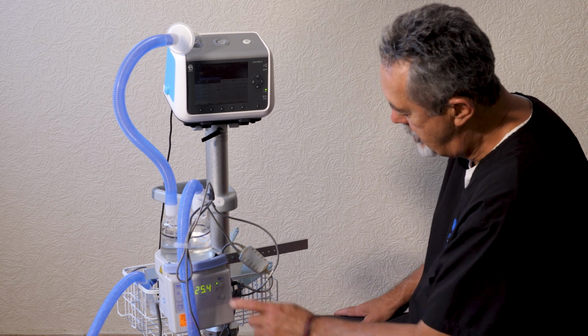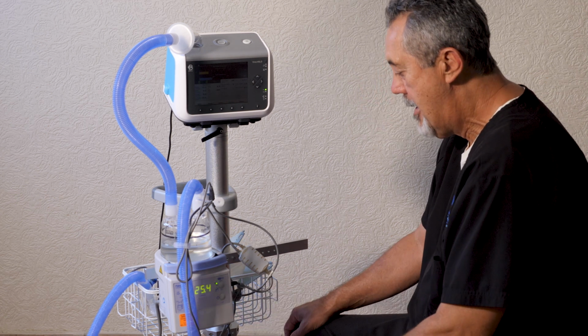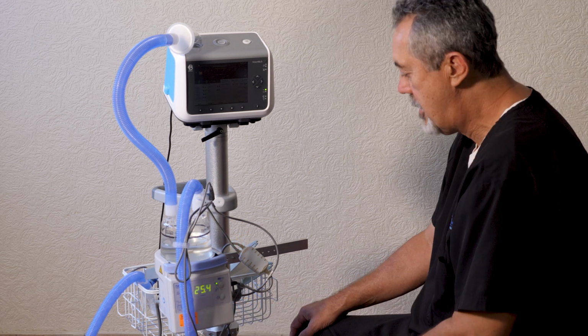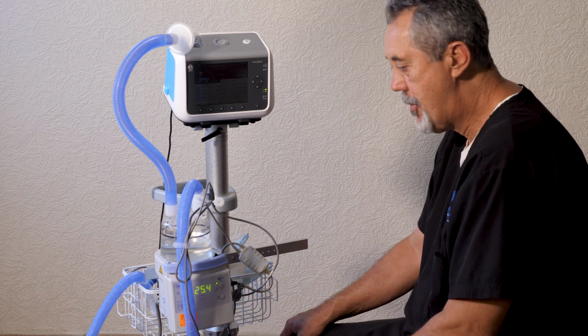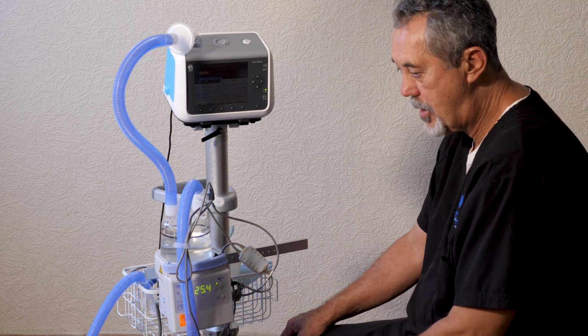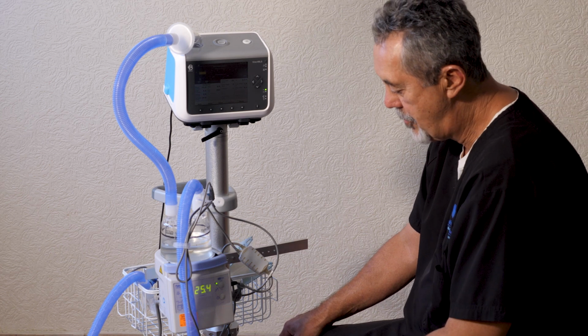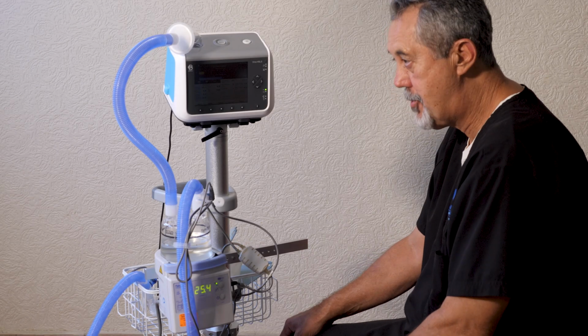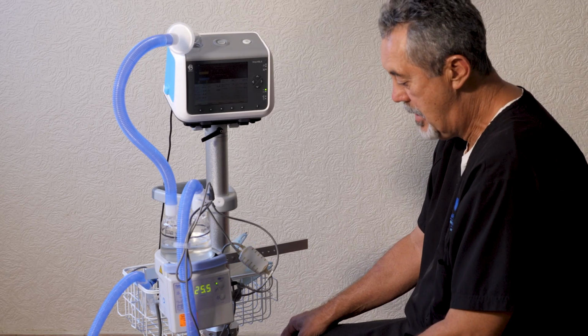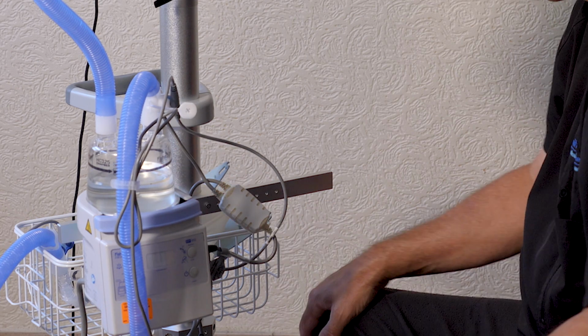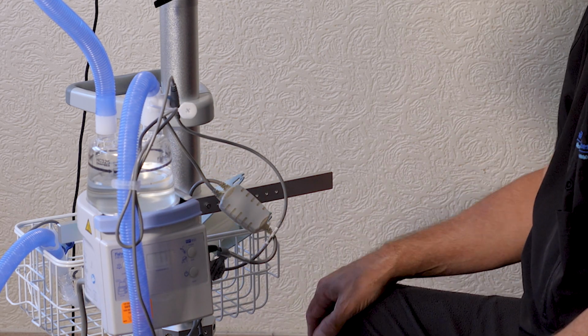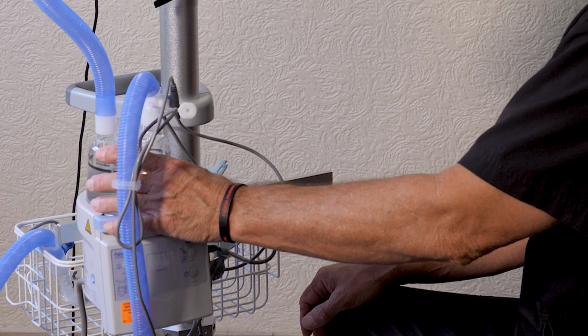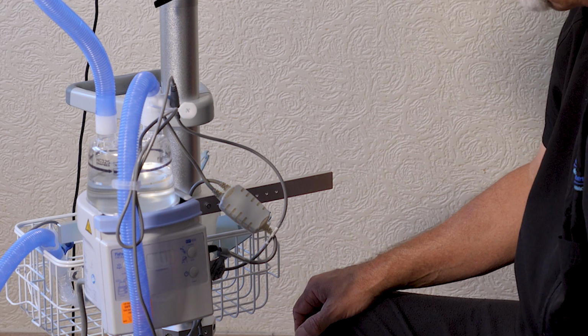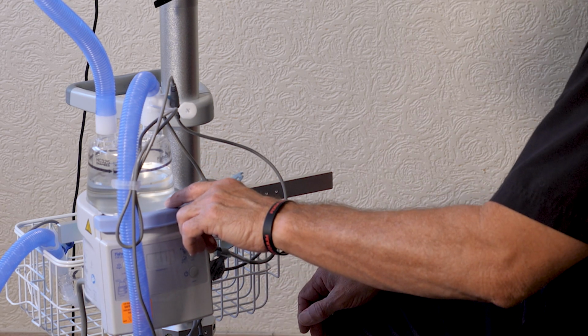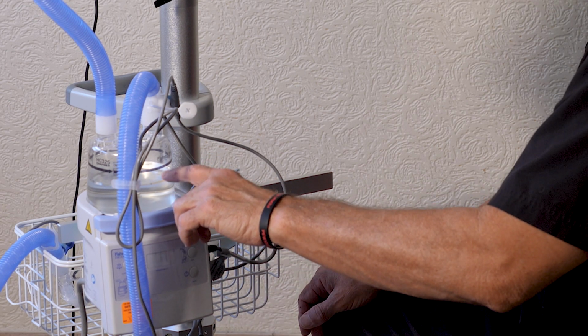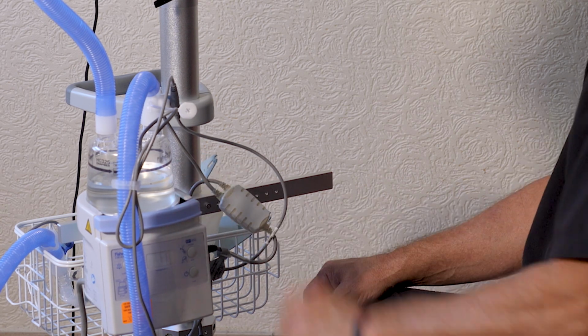All right, so we turned it on. It's going to go up in temperature. The temperature on the humidifier is going to typically fluctuate between 35.5 and possibly go up to even as high as 39 degrees. But the average temperature should be right around 37. All right, troubleshooting the humidifier. If you get an alarm, the first thing you want to do is make sure you have plenty of water in the water chamber. And what I mean by that, you don't just want to have a couple of centimeters on the bottom. You want to have it at least halfway full or just underneath the full mark.